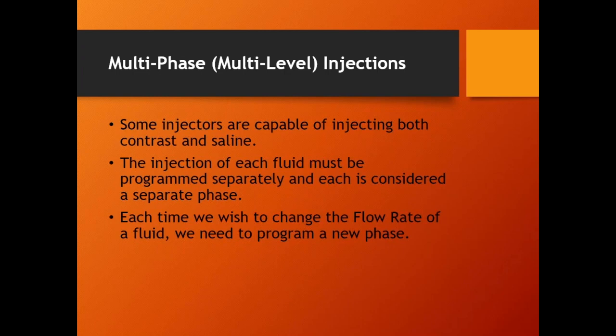Now these 4 rows are called phases. There's one older model that calls them levels, but universally these are called phases. This first phase, this first line, is green and it's 5 and 20. Green means contrast. 5 means a flow rate of 5 milliliters per second, with a total of 20 milliliters. That's the first phase. Each phase is a separate injection, but we do all this with one click of a button. One injection does this whole thing. This isn't 4 injections, it's 1 injection with 4 different phases.